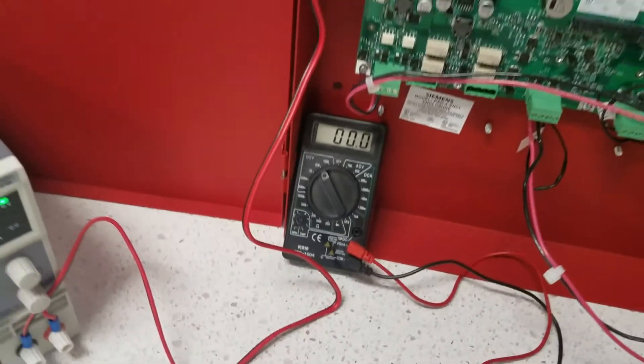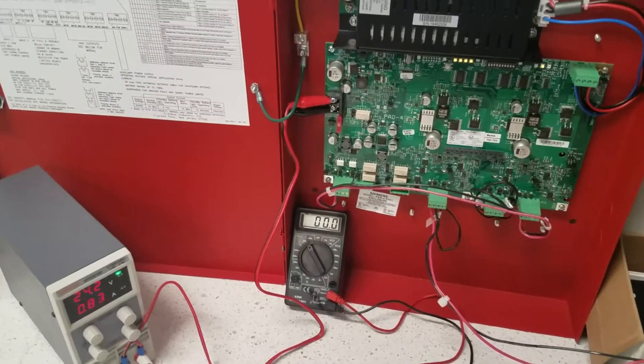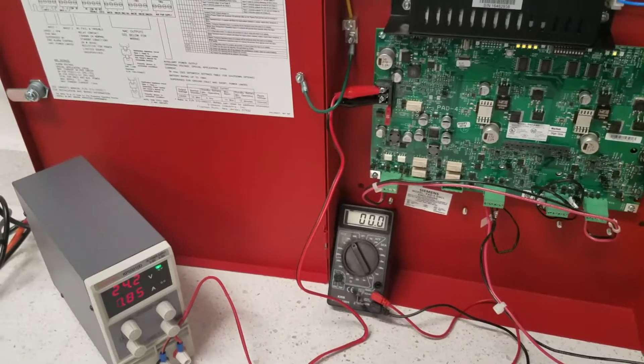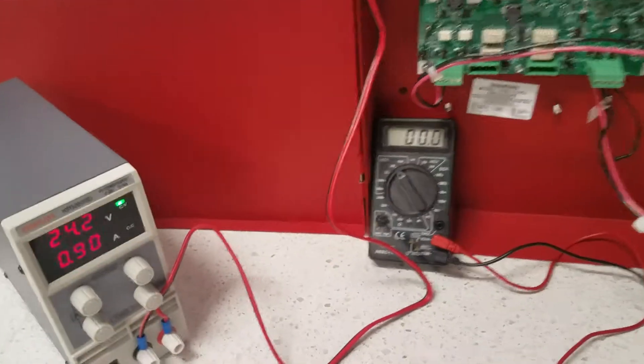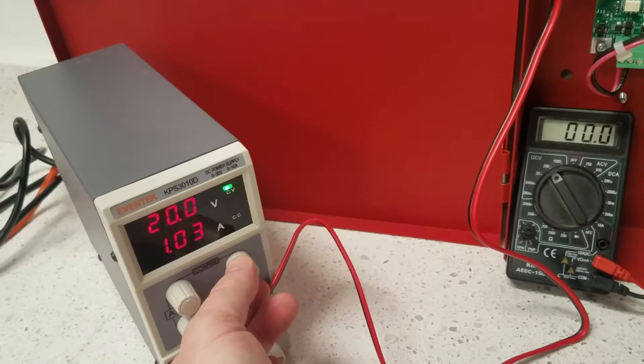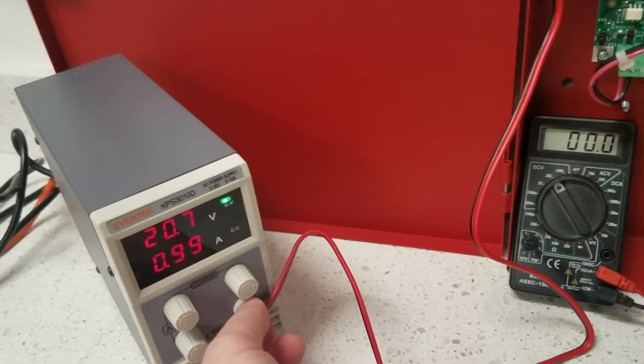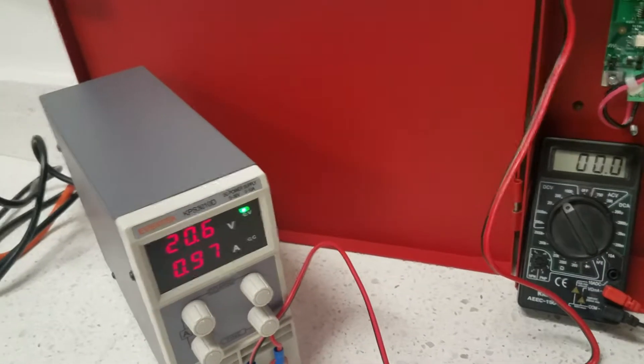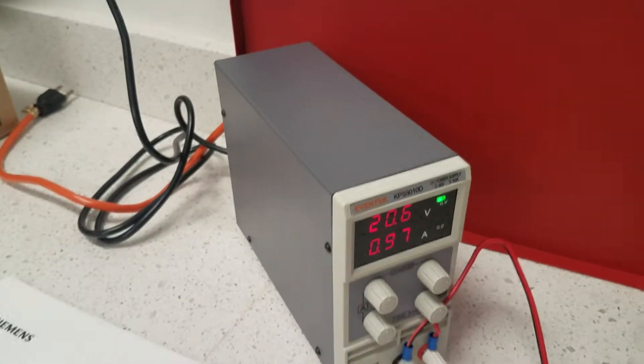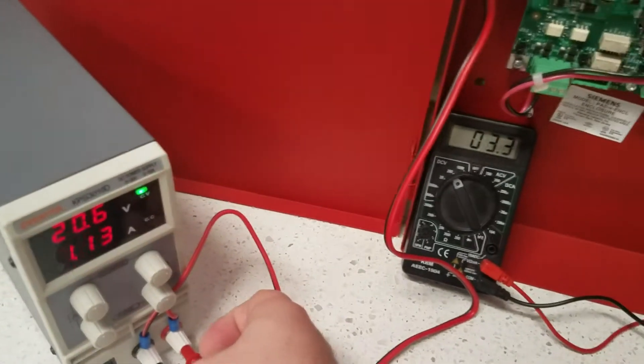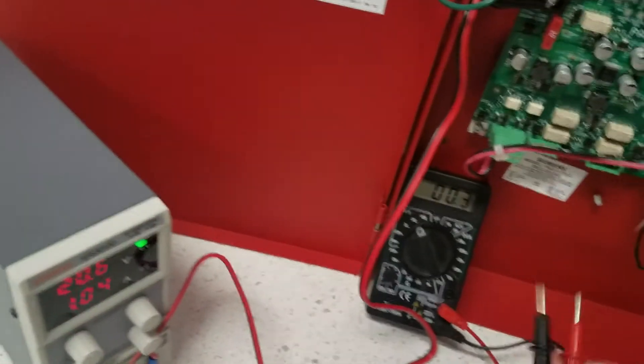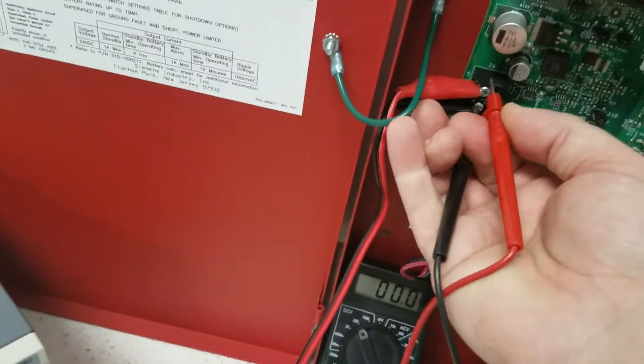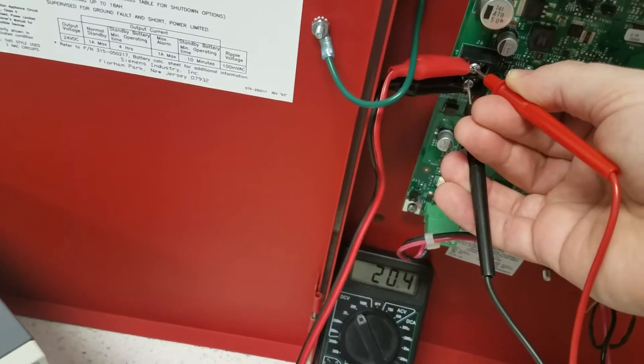Now, what we're testing for is what happens when the batteries are at end of useful battery life. And that is per NFPA 72, 85% listed voltage. So let's take this down to the 85% listed voltage, which is 20.4 volts. Now, the other one was off by 0.2 volts, so it should be at 20.6. 20.4 volts even. And just to verify on the power supply itself, 20.4 volts even.